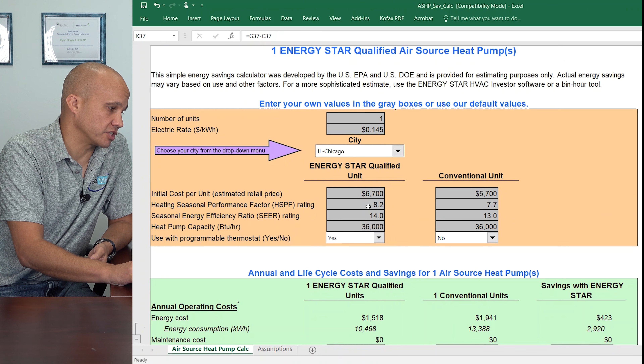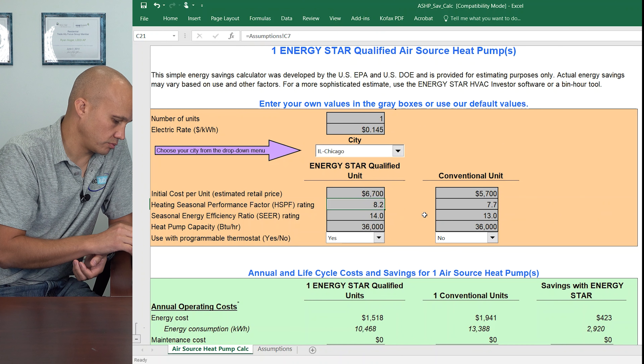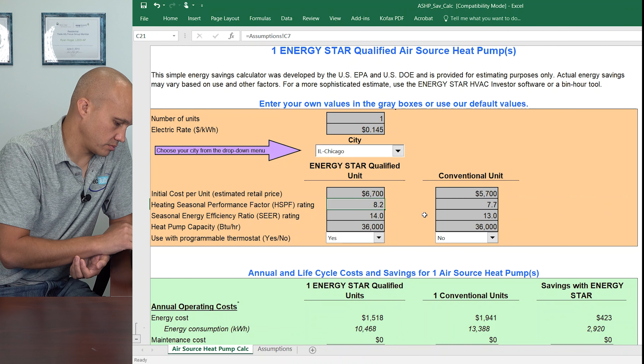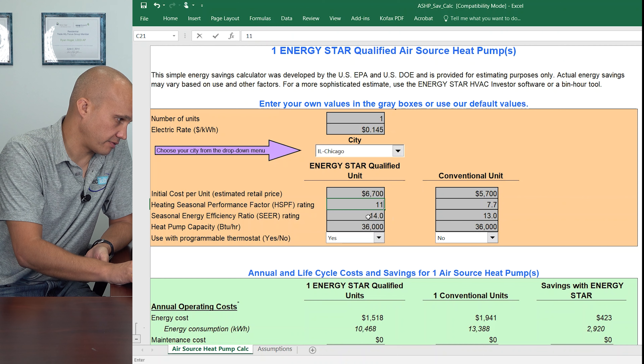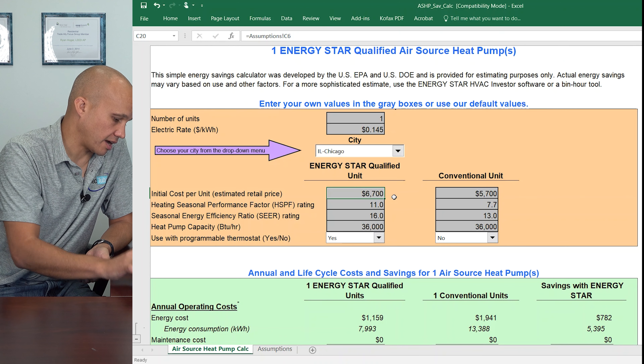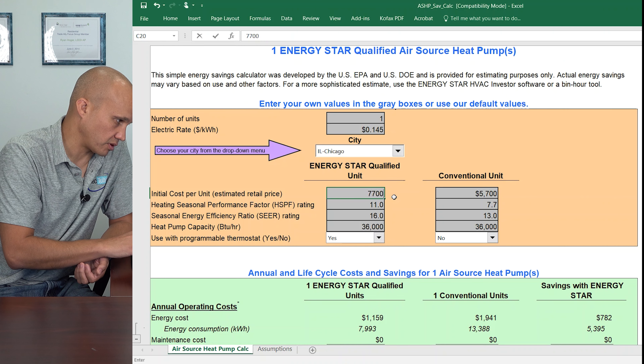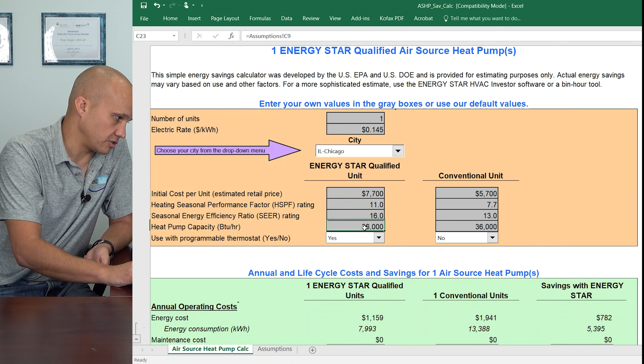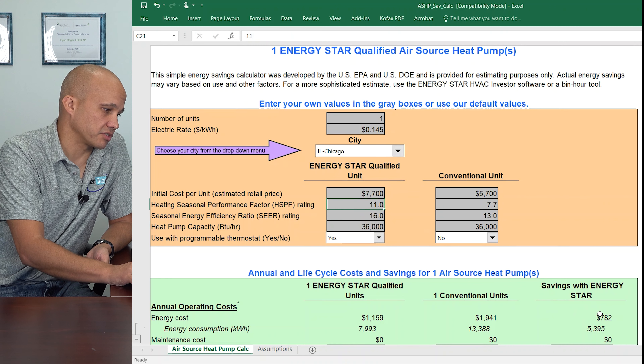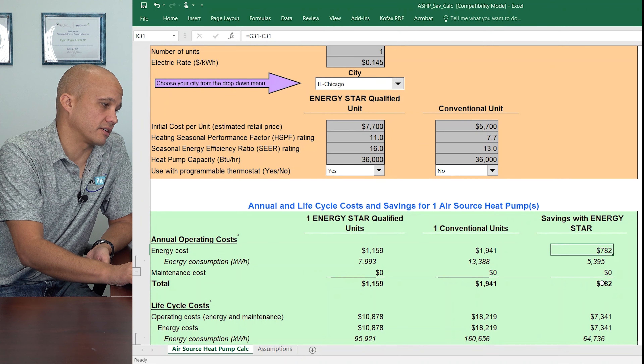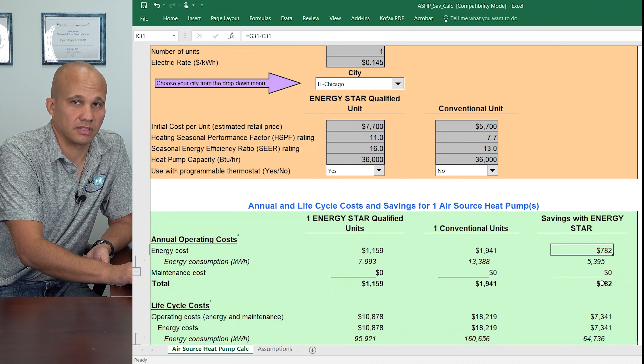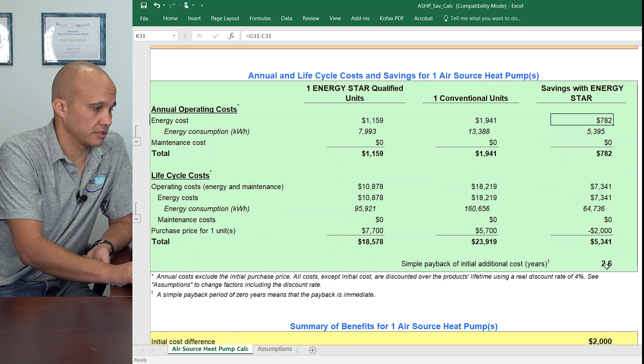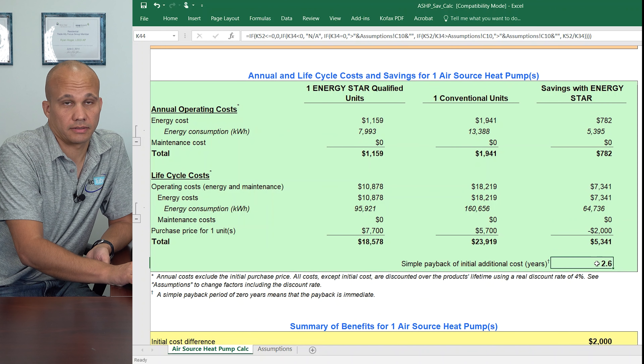I could go in and put a more efficient system in. Let's do 11 HSPF and 16 SEER. I don't know what that costs, but let's just say it costs $1,000 more just for argument's sake. These are both three tons in this example as well. So now it's going to save me $782 to make this upgrade, with a 2.6 year payback.